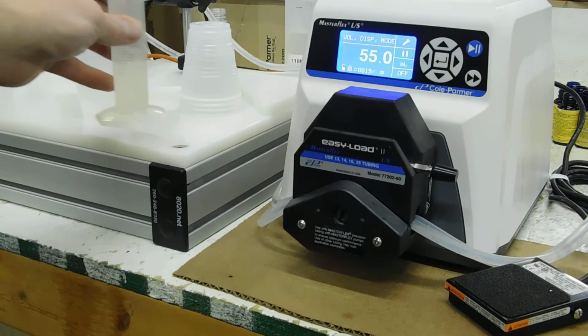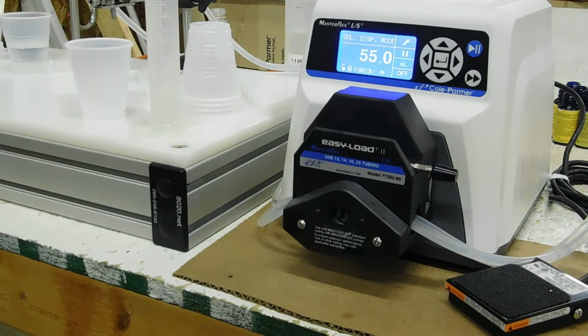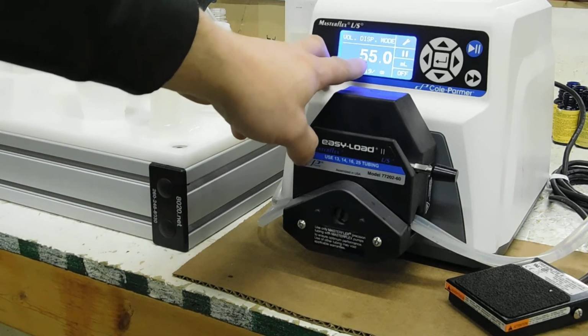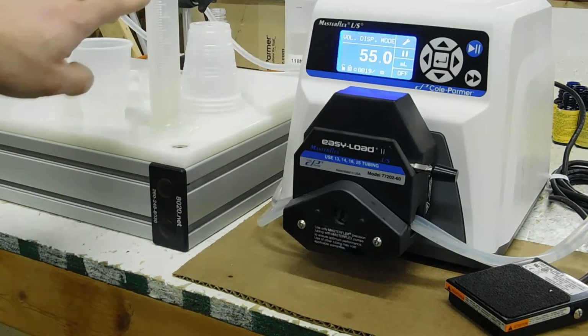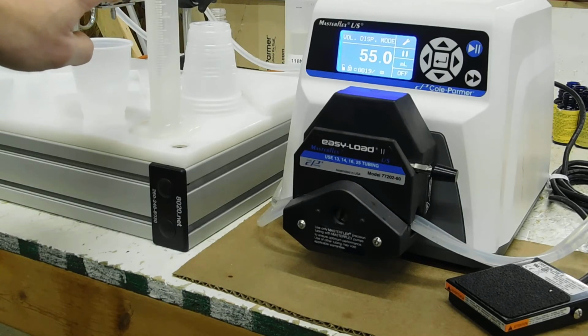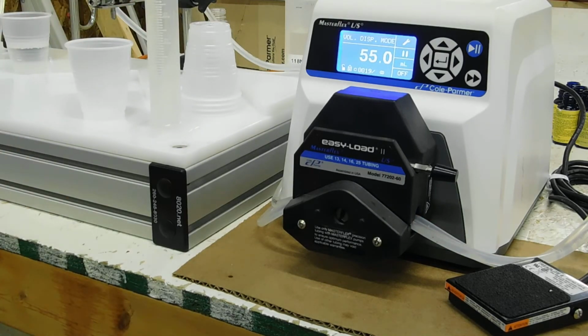And as you can see, I got just a little over 55 milliliters. So what I can do to make the correction is go through the tubing calibration again until those numbers jive correctly. So from here, 55 mil, if I'm getting a little bit higher or lower here, that means I need to go back into my tubing calibration screen and do the tubing calibration again. Sometimes to zero in on an exact tubing calibration or dispense volume, you have to run the tubing calibration more than once.